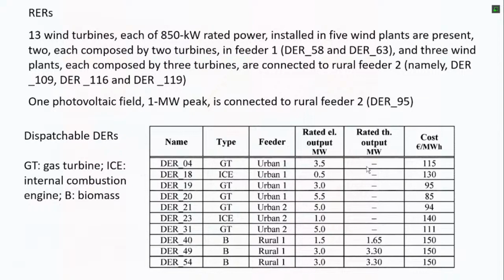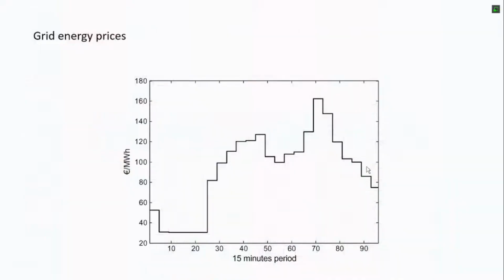You see the values of power that are limited. Since the network is 15 kilovolt, we cannot think about installing several tens of megawatts; we need to be lower than 5 megawatts typically, maybe 5 or 6, but not much. So these are the profiles of energy prices that follow the market, the wholesale market.